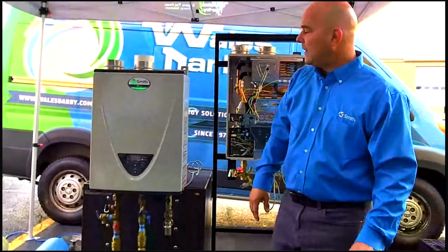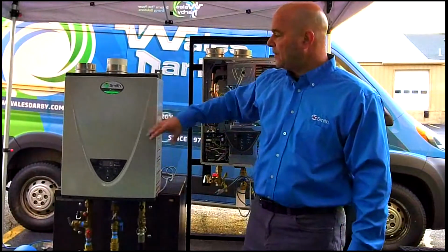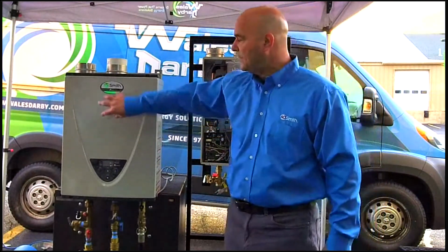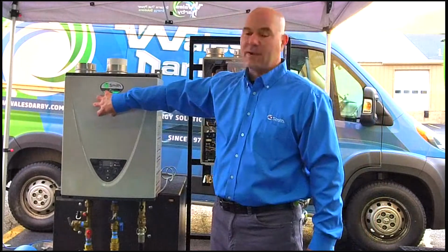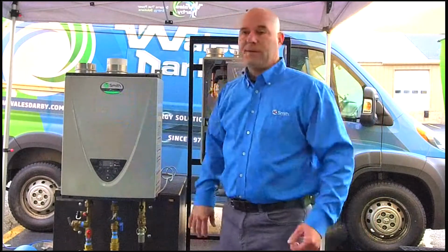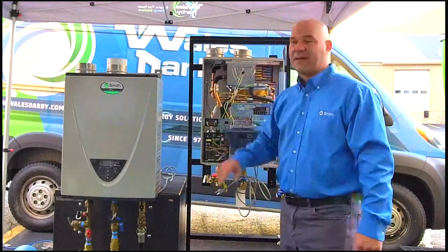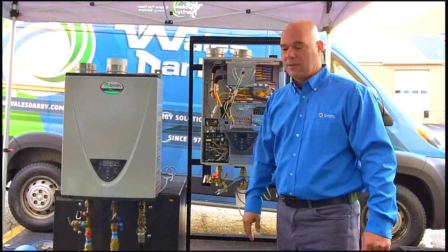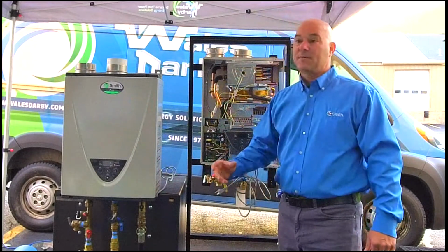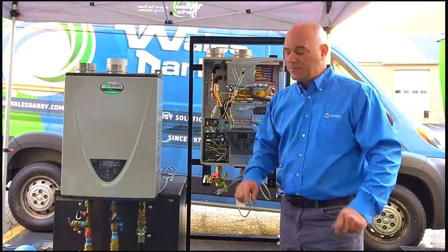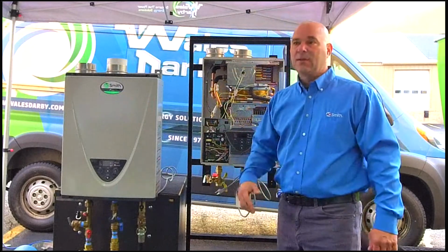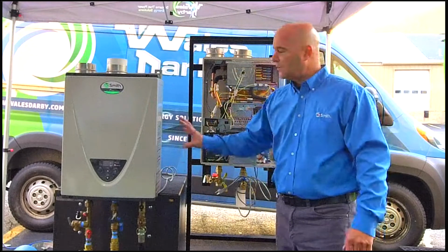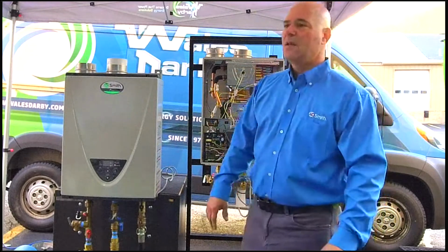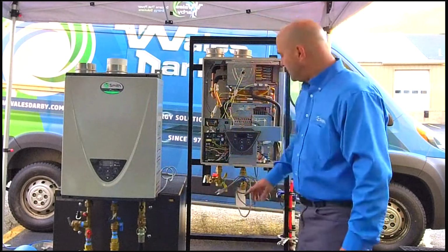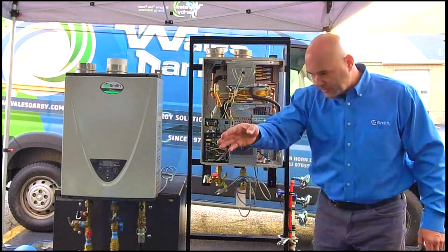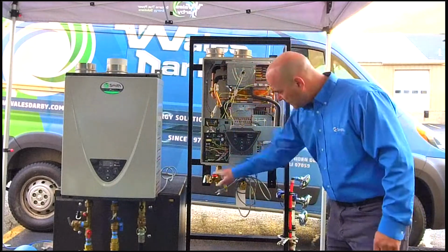We have indoor and outdoor units. This happens to be an indoor unit. We do have these for outdoor use. There would be a vent termination right here on the outdoor use ones, and don't expect them to live outside at 0 degrees. They just won't last. We do have some heaters strategically placed throughout the inside of the unit, but again, don't think they're going to keep it from freezing. It is strongly recommended on every job: product preserver, valve kit on every job.